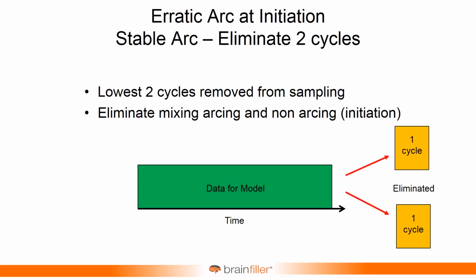For the next edition of IEEE 1584, all of the data was analyzed, and it was placed sequentially from maximum to minimum, and the 2 lowest cycles were kicked out. And that's when you get into this basically mix, where it's partly a bolted short circuit, the wire is melting, the fuse wire, it's transitioning to arcing, it's really erratic, and it actually behaves a bit unbalanced, which is why grounding factored into this, because you had a bit of an unbalanced current there in the beginning. So the new equations are based more on the stable arc, and because of that, there's no difference between whether your system is grounded or ungrounded. We'll call it one size fits all when it comes to grounding for the next edition of IEEE 1584.